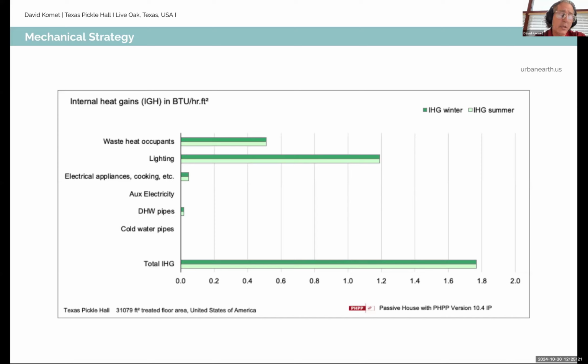This is of particular interest to me. I'm sure many of you have seen the 24-volt DC microgrid approaches and what's going on now in low voltage lighting. I looked hard into low voltage lighting to try to cut this internal heat load. We had a design solution, but we're not quite there yet, though getting really close. Bringing a low voltage system in, so we're not stepping down from 120 to 24 or 12 at the light fixture and throwing off waste heat, would be a fantastic opportunity for a facility like this to really cut that lighting load.